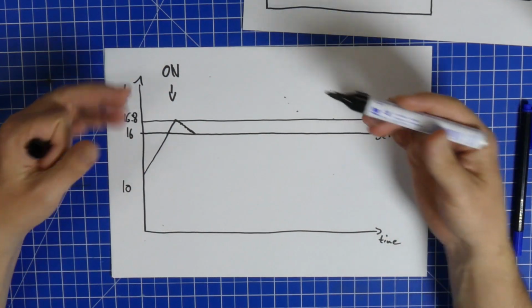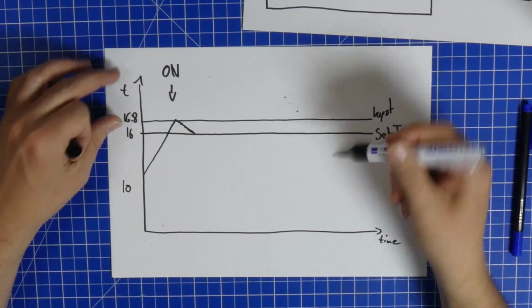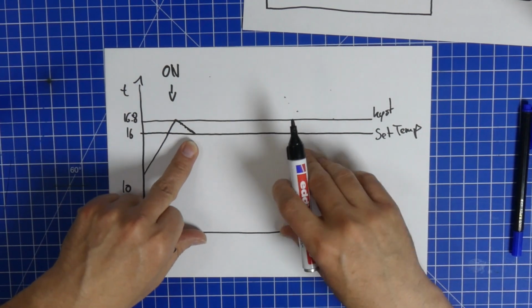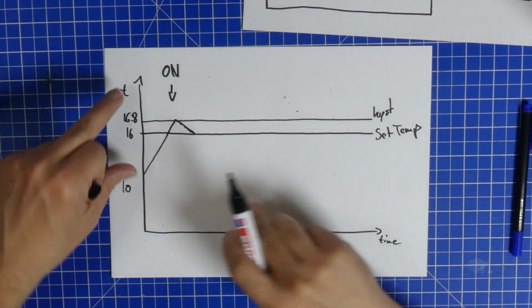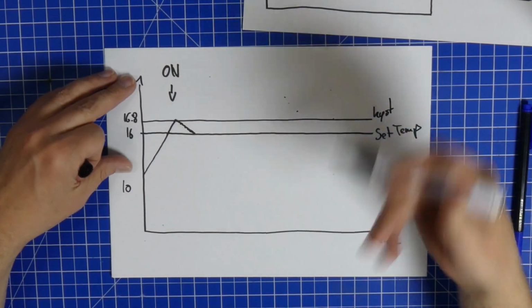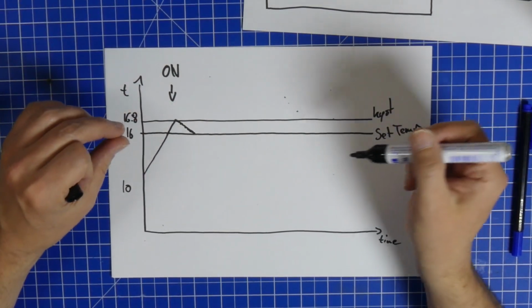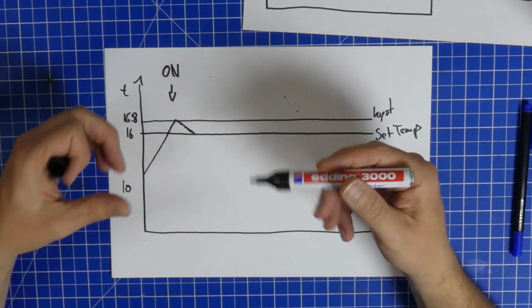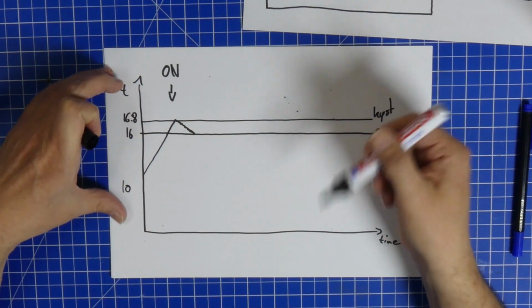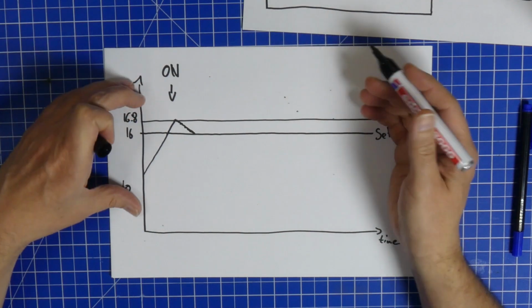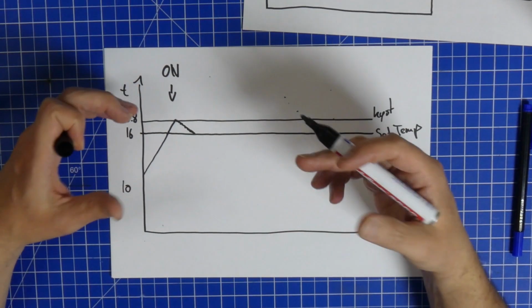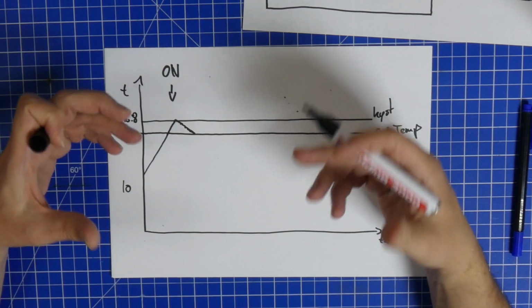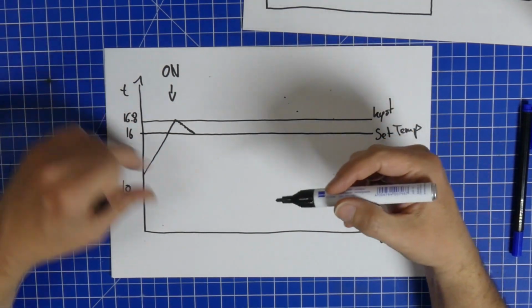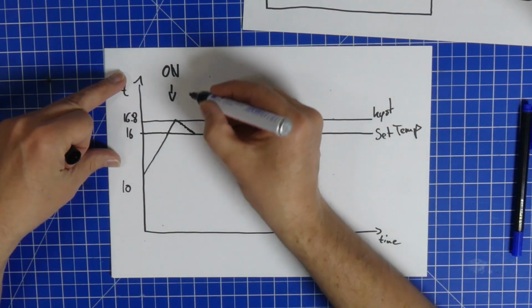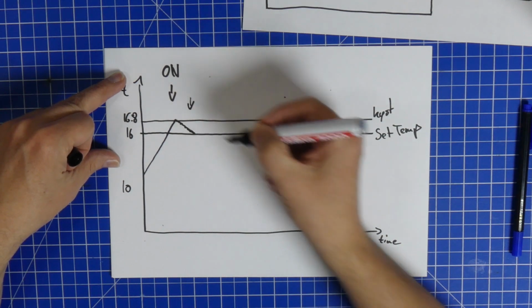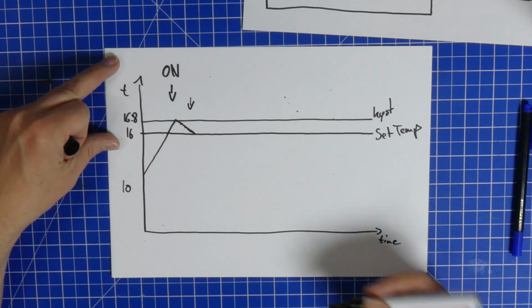Now, in a normal AC, you would say, okay, now is the time to turn it back off again. And then it would heat back up again, and you would turn it back off. This leads to something that is called a massive on-off situation for an AC, because starting the AC and stopping it is basically the thing that has the most wear. So what happens at this point, right here, is that the bypass valve opens.